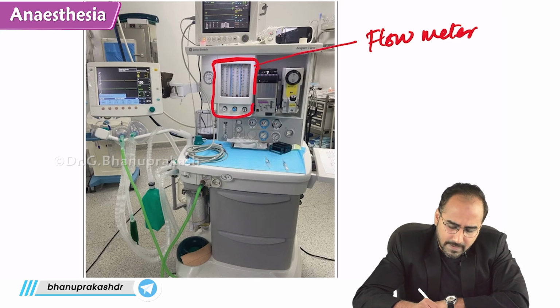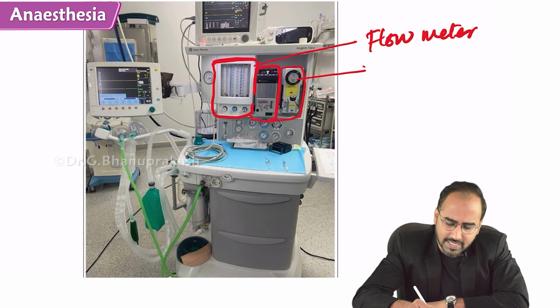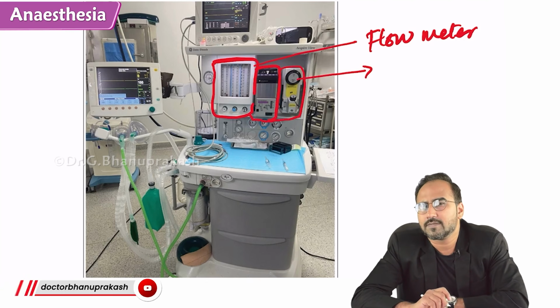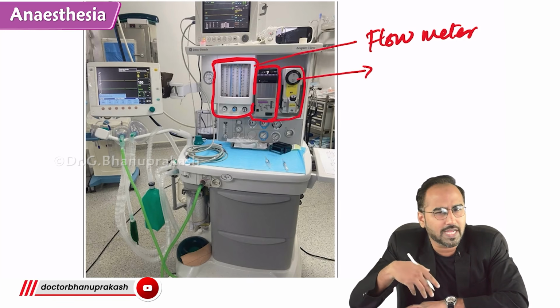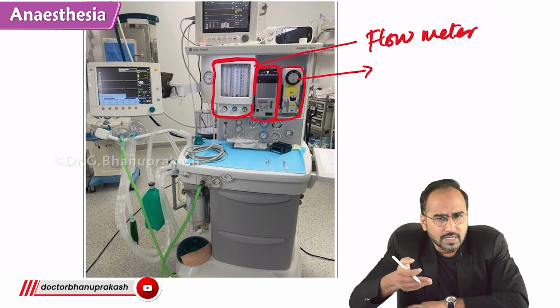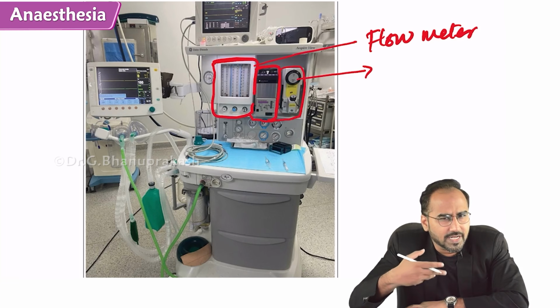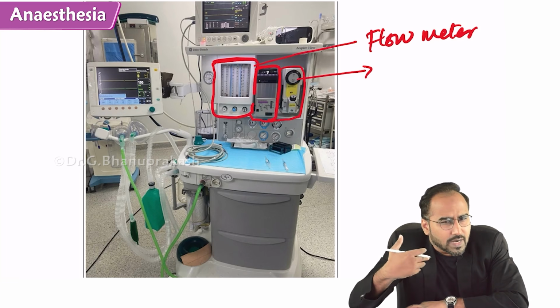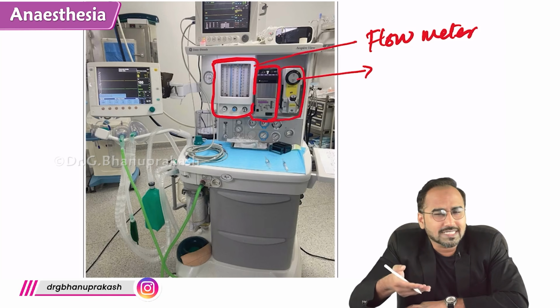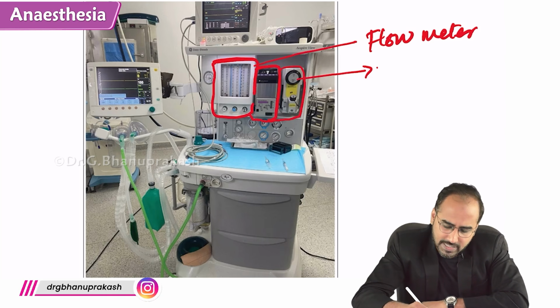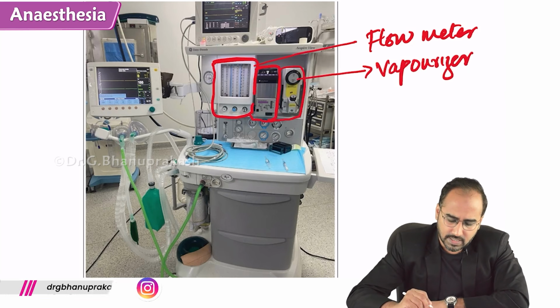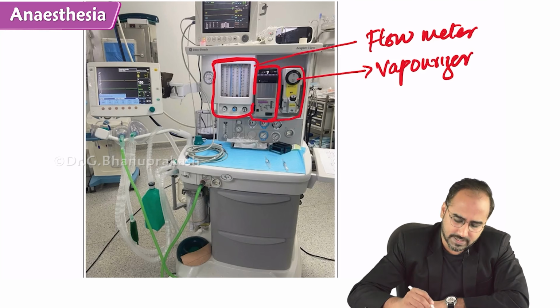Now, just beside the flow meter, you see a container that stores the liquid inhalational agent. What is this container called? Come on guys, put some pressure on your brain, not on your pages. When you do, you will realize that the special device that stores the liquid inhalational agent is called the vaporizer. This part of the machine is called the vaporizer.